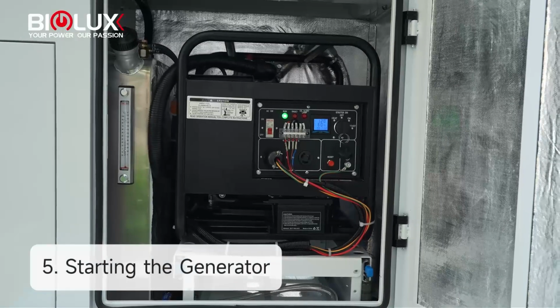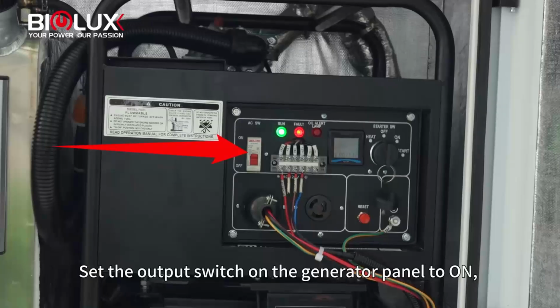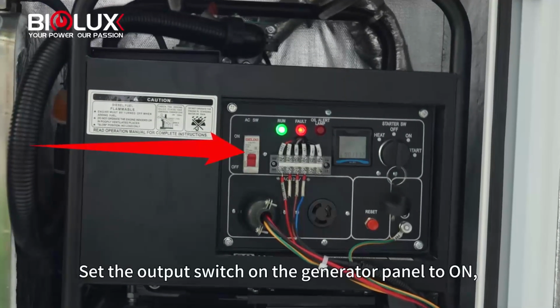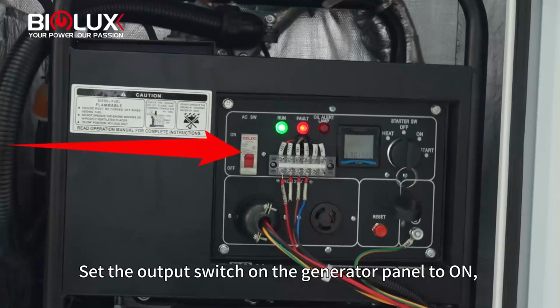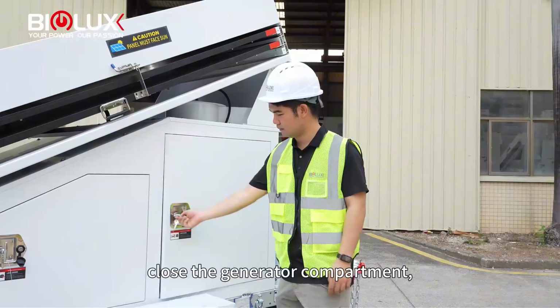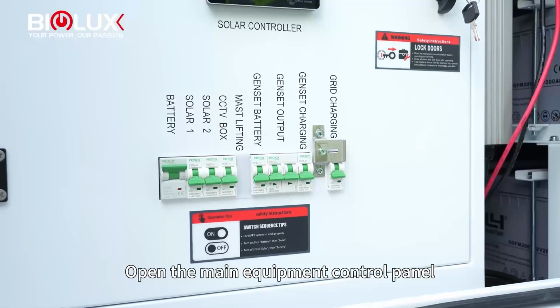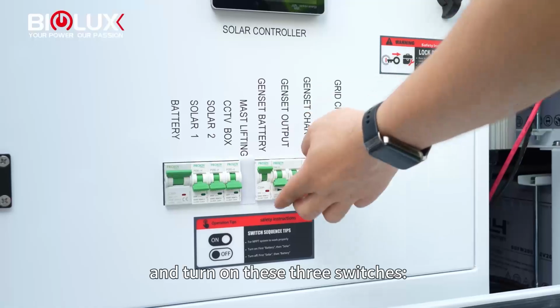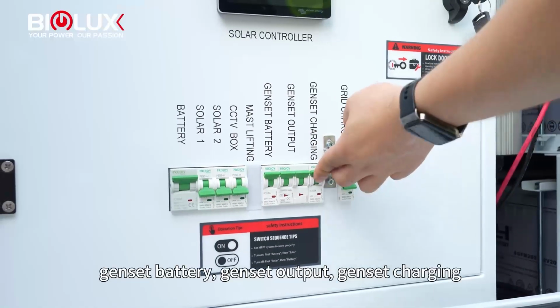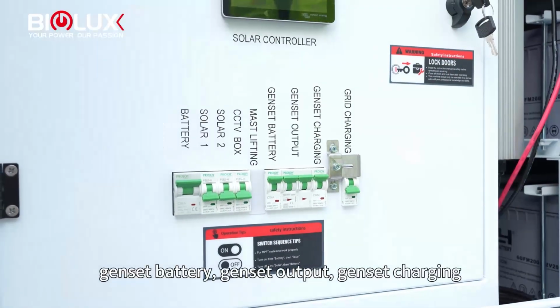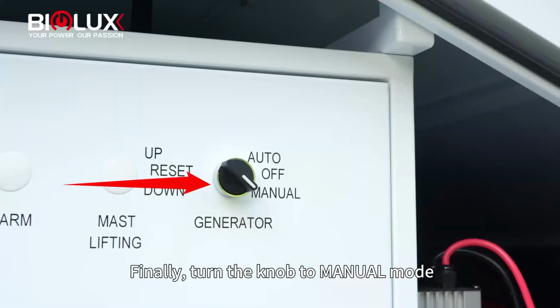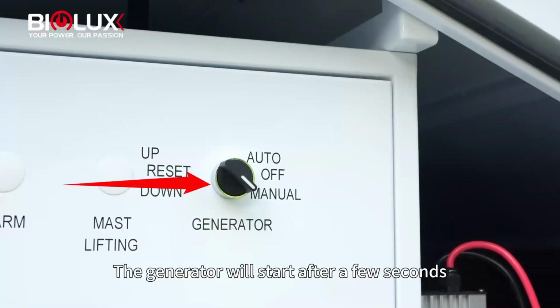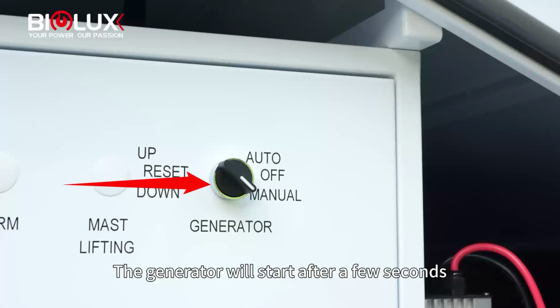5. Starting the generator. Set the output switch on the generator panel to on. Close the generator compartment. Open the main equipment control panel and turn on these 3 switches: genset battery, genset output, genset charging. Finally, turn the knob to manual mode. The generator will start after a few seconds.